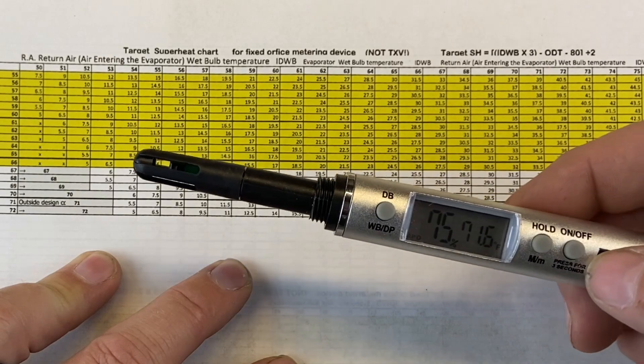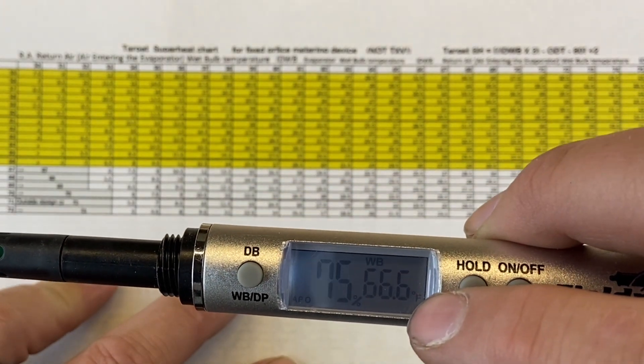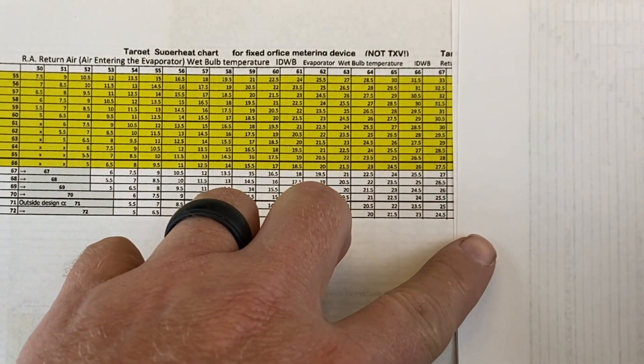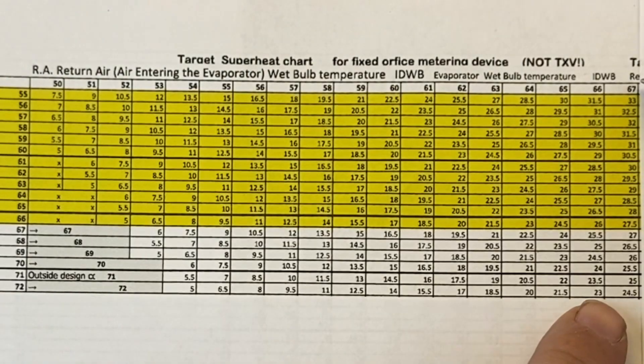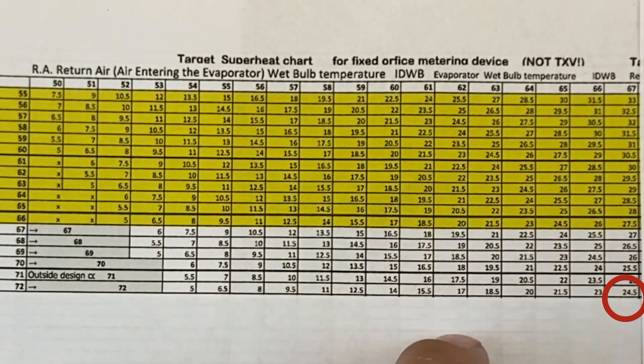Now I set my thermometer for wet bulb temperature. It reads 66.6 — we'll round that to 67 degrees Fahrenheit. This is the return air entering the evaporator coil. So on the chart we find 67 degrees down the side. With a 72°F outdoor temperature and a 67°F return air wet bulb, where those two numbers cross, our target superheat is 24.5 degrees. That's what we want our superheat to be under these conditions.